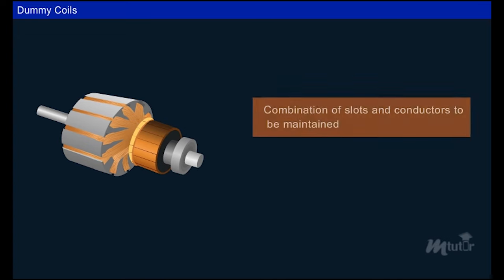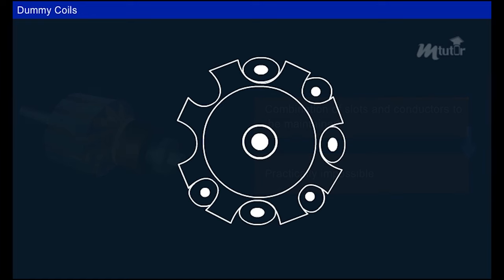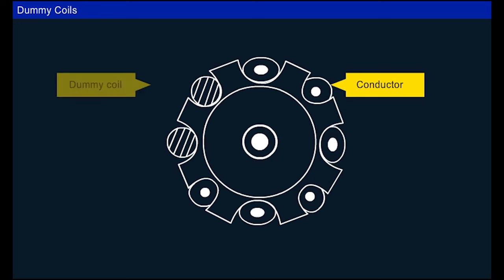For winding a wave type armature, there must be a combination of a particular number of slots and conductors in the armature. Practically it is not possible to always meet such design requirements, so to provide mechanical balance to the machine, one or more coils may be inserted in appropriate slots, electrically insulated from the other windings. Such coils are called dummy coils.